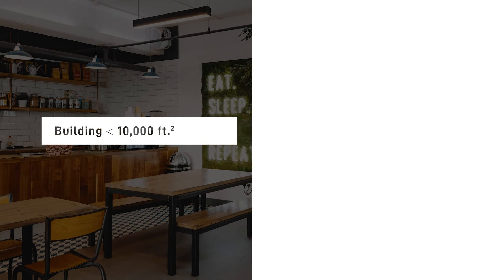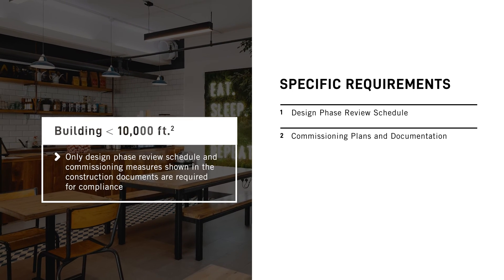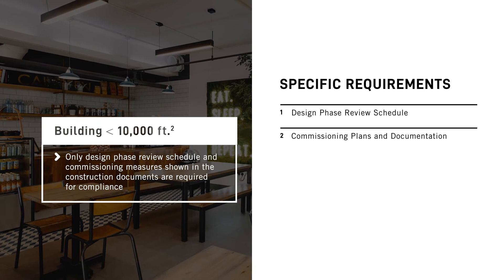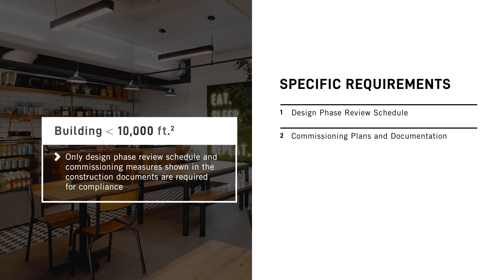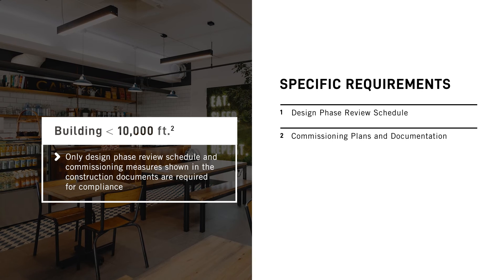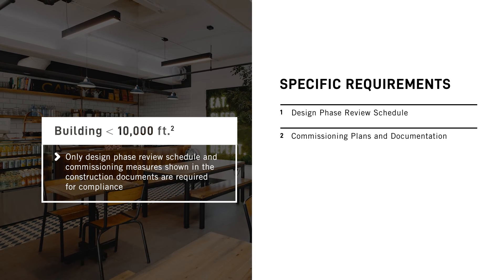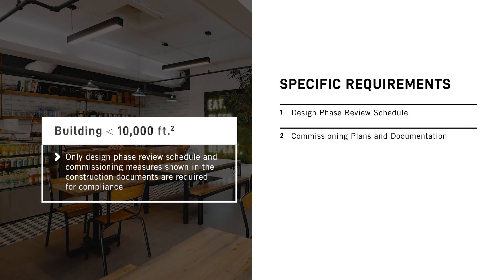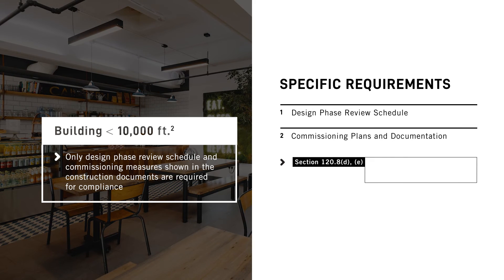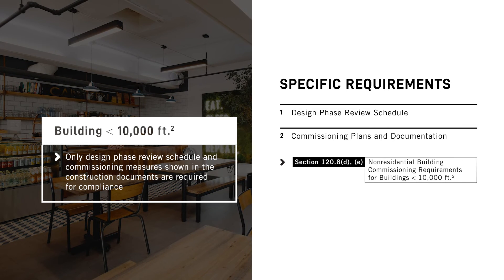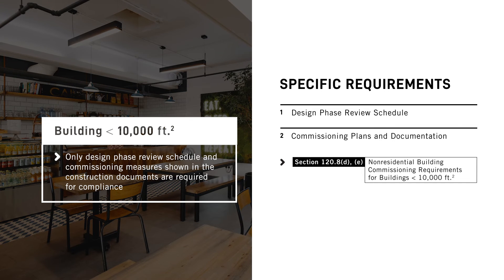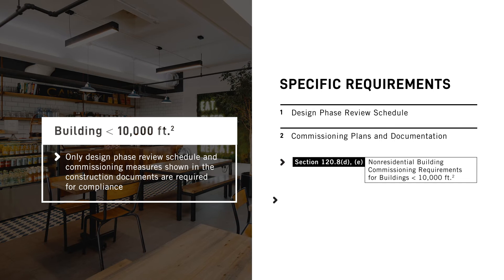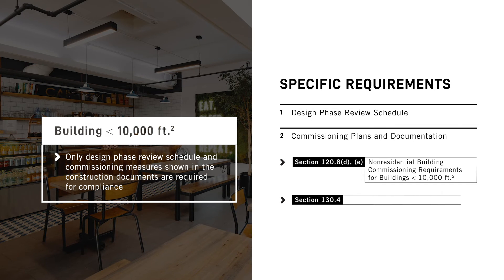For buildings less than 10,000 square feet, only the design phase review schedule and commissioning measures shown in the construction documents are required to be in compliance with the Energy Code. While functional performance testing doesn't have to be documented as part of the commissioning process described in Section 120.8 for buildings less than 10,000 square feet, acceptance tests still need to be conducted to get an occupancy permit. This is outlined in Section 130.4.